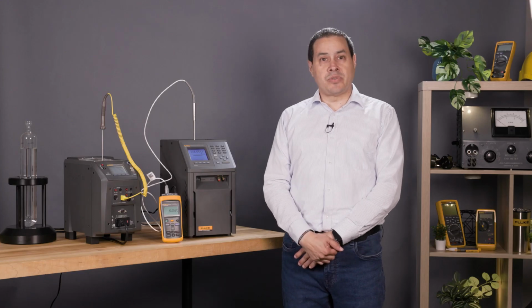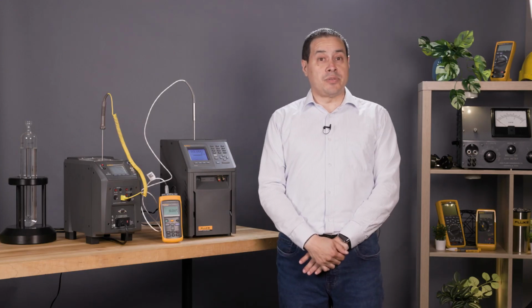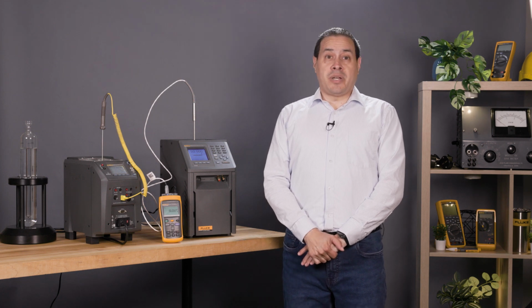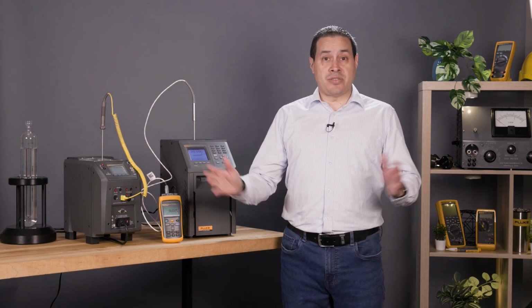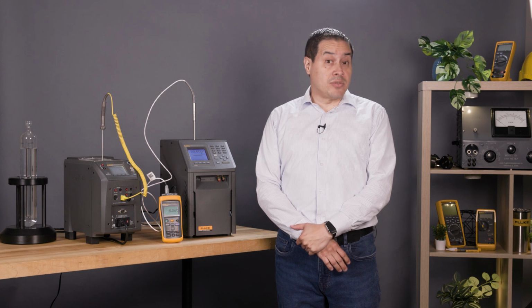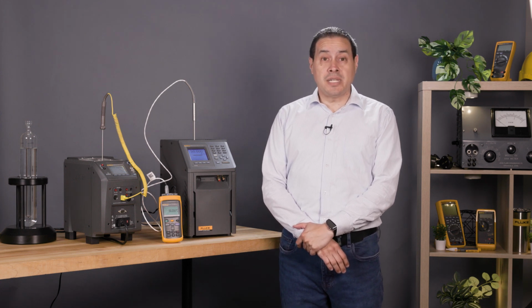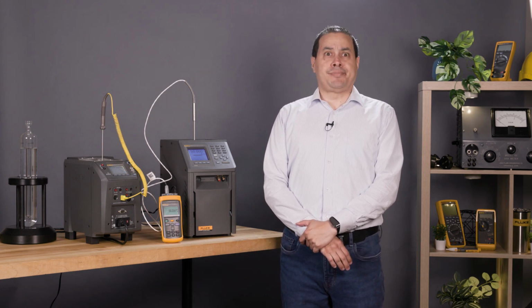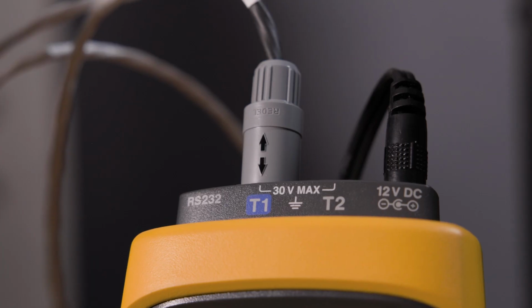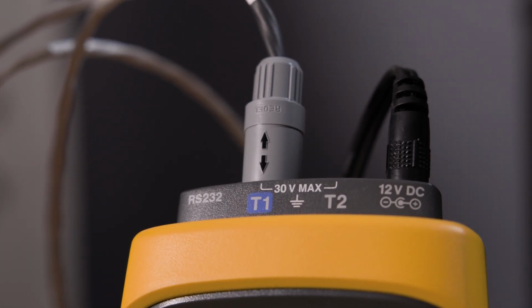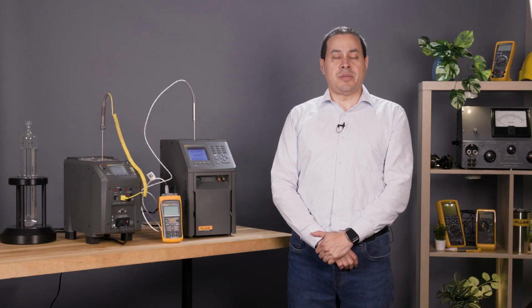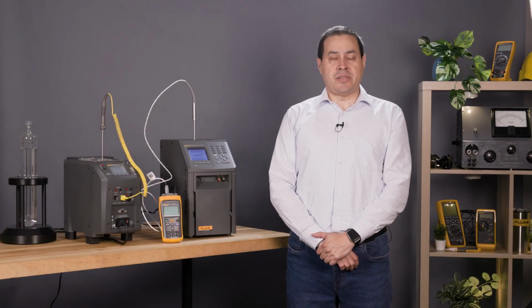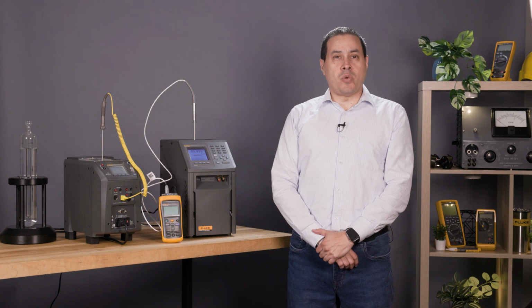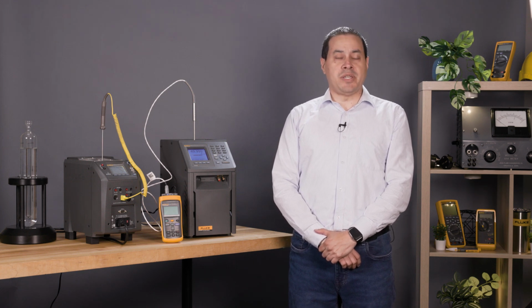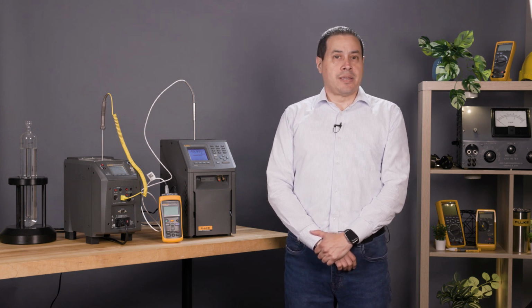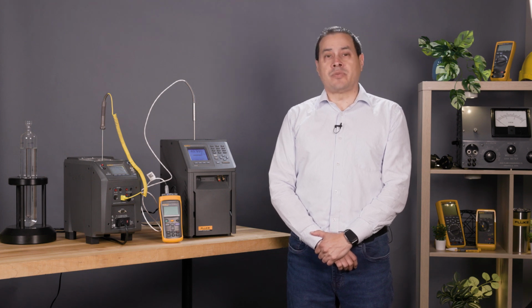If you want to reach high temperatures, you need a 9173 probably to get 650 Celsius. But if you want to go lower, there's always ranges between minus 200 C, up to 0 C, up to 650 C. So it depends on your application. There's no way we can go to really low temperatures and high temperatures, so we need to keep to the ranges. So depending on the range and the application, there's always models. There's no way one size fits all. So you need to be covering at least 80-90% of the workload for the first one, and then try to add more dry wells to your collection.